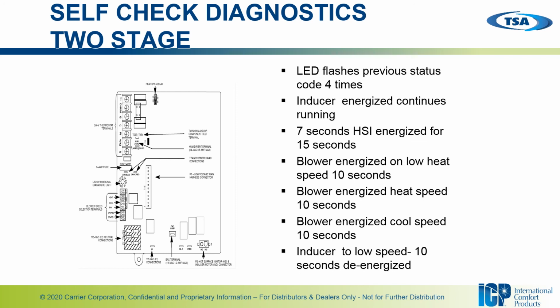All right, and on the 2-stage models, like the single stage model, your LED is going to flash the previous status code 4 times. Then you'll get your inducer starting up, and 7 seconds later you'll get the hot surface igniter, so be on the lookout for that igniting up and lighting up bright. That'll take place for 15 seconds. Following that, your blower will energize in the low heat speed for 10 seconds. Then the blower will energize in the normal heat speed for 10 seconds, or high heat speed for 10 seconds, if you will. Then you will go to your cooling speed for 10 seconds. And then following that, the inducer will drop to low speed for 10 seconds and then de-energize.